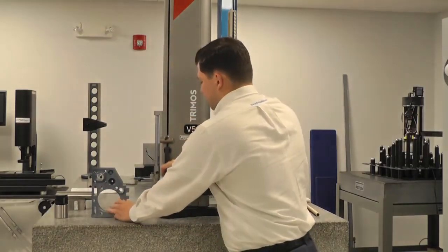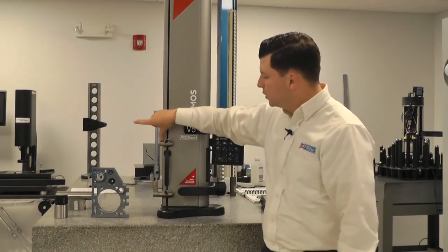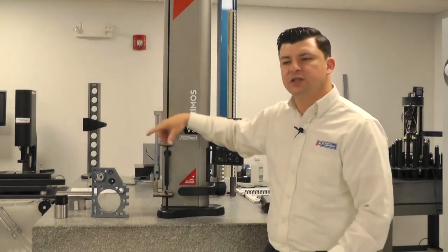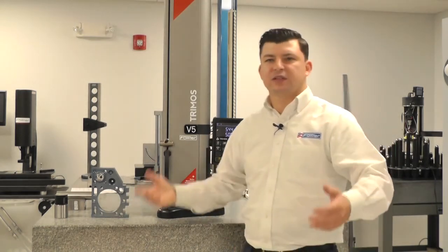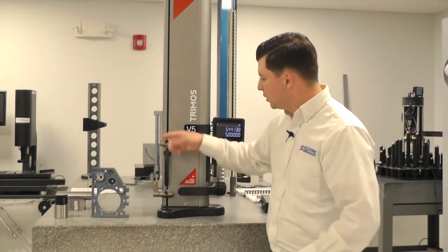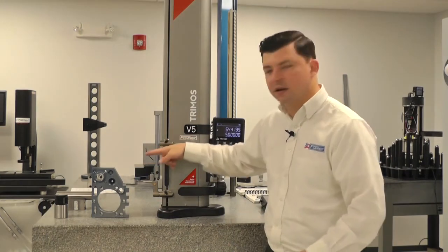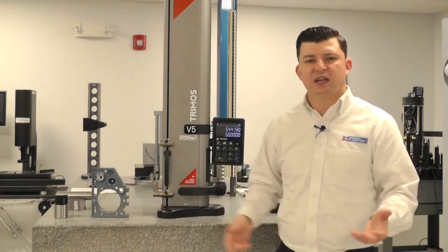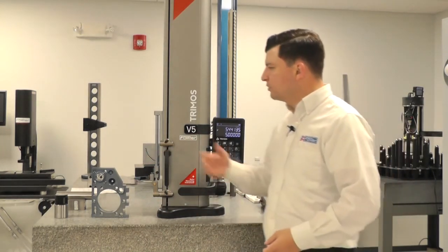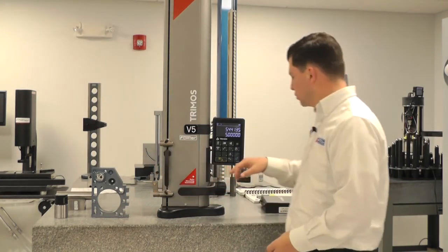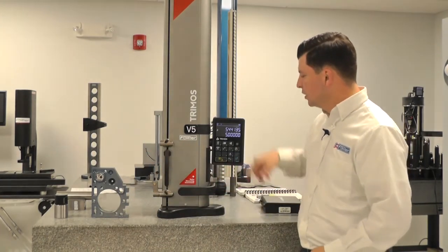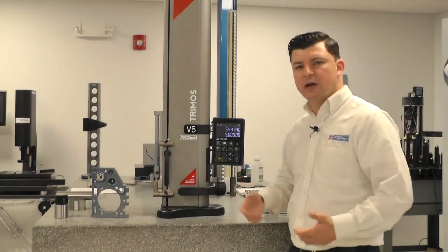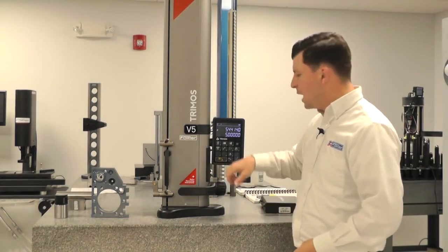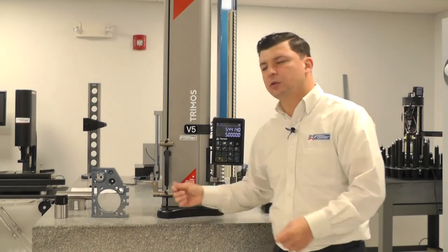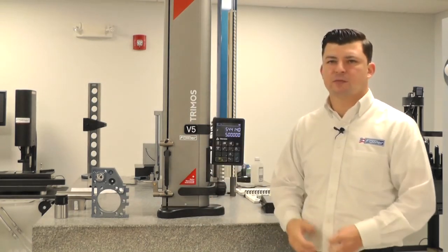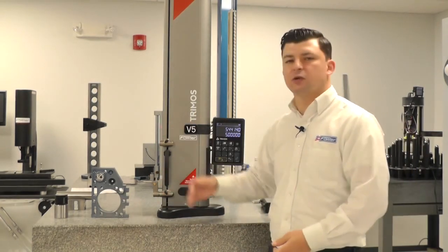So that's how you're going to establish a preset. If you were utilizing your maximum application position, you could just establish a preset with, say, a 12-inch gauge block. Or maybe in the standard position in the secondary holder, you maybe use an 8-inch gauge block. So whatever gauge block or known height you have, establish a preset value, hold down that button, tell it what value you want to store it at, engage your probe, tap your preset button to engage that value, and now you've expanded your measuring range by however much in whatever position you're holding.